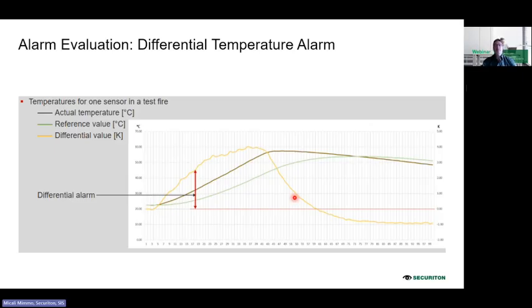Then very important is the alarm evaluation, which we call the differential temperature alarm. 95% of all the alarms in a fire are always because of the increase of the temperature and not because we reached the maximum temperature. So the increase of temperature is very important because this will determine how fast we can react, or how fast the system has to react in case of a fire.